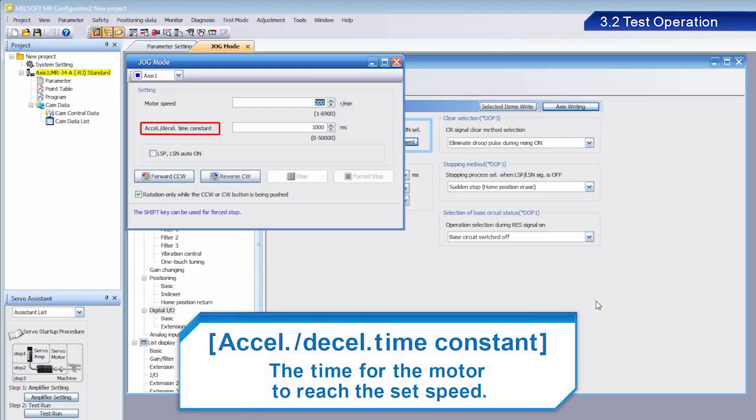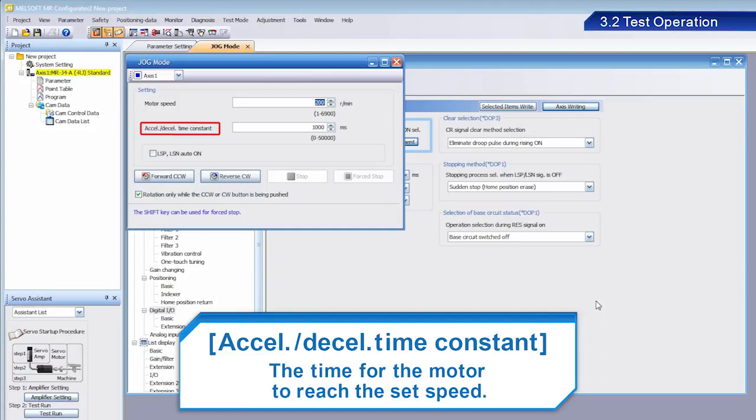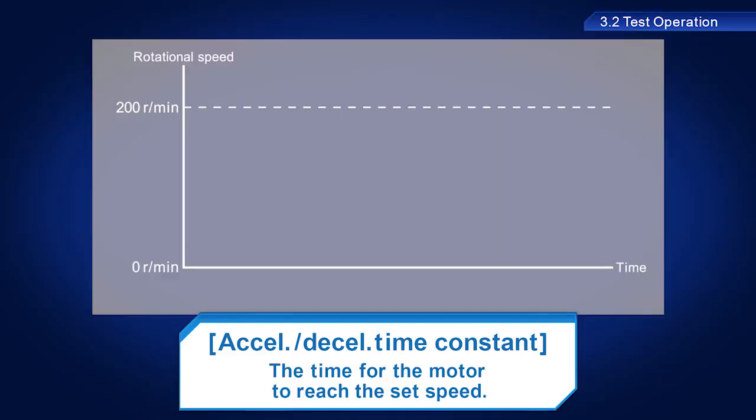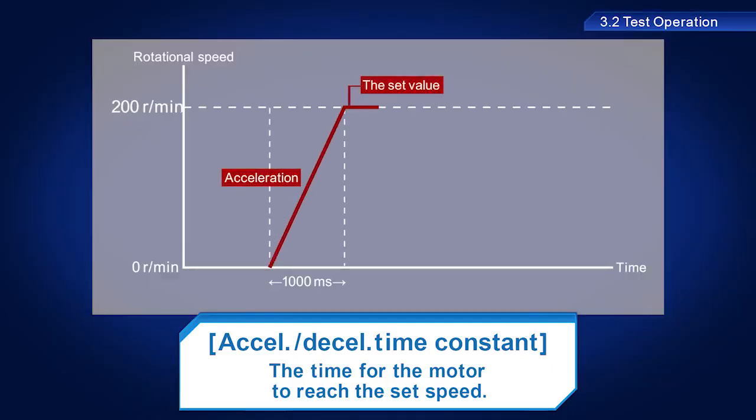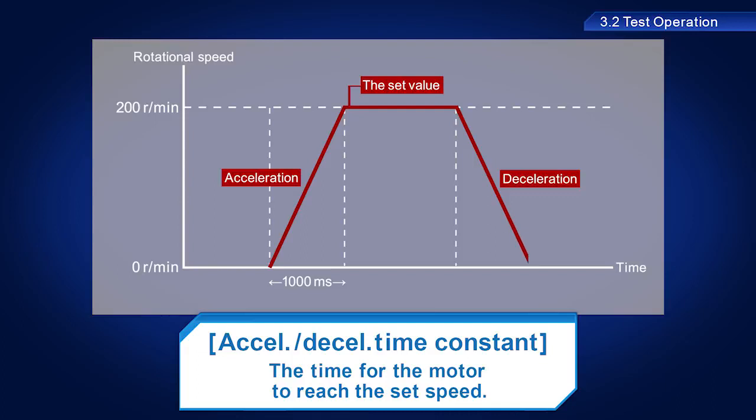Acceleration-deceleration time constant sets the time for the motor to reach the set speed. This is also the time used to decelerate the motor to a stop. For this training, we will set a value of 1000 milliseconds.